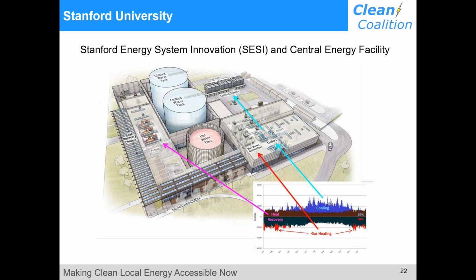They designed the Central Energy Facility, which is what you see here. One of the things that really occurred to Stanford as they were assessing their needs is that there's a nearly complete overlap between their heating needs and their cooling needs. The graphic on the bottom right shows you that. During the summer months there's quite a bit more need for cooling, but they realized there was no sense in taking energy to heat at the same time they were taking energy to cool.